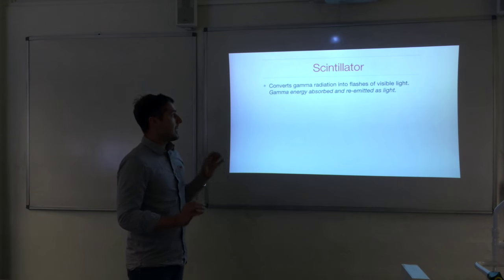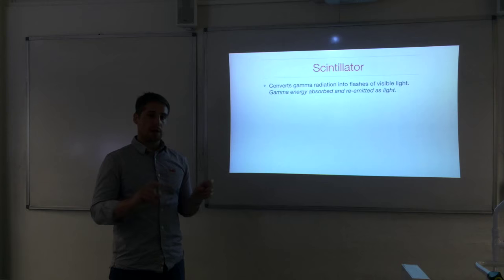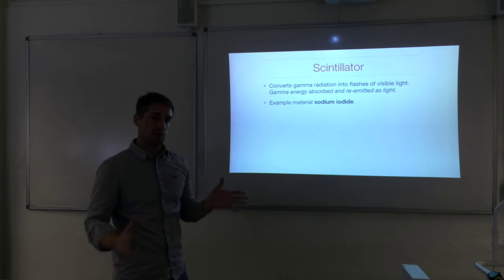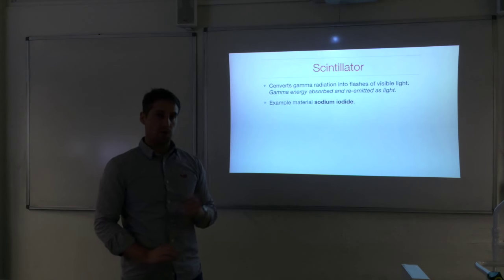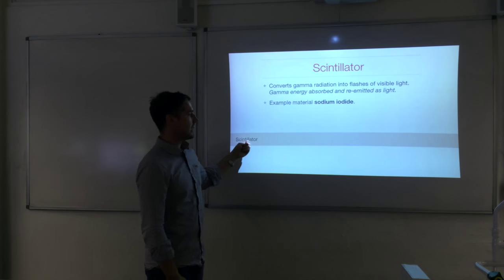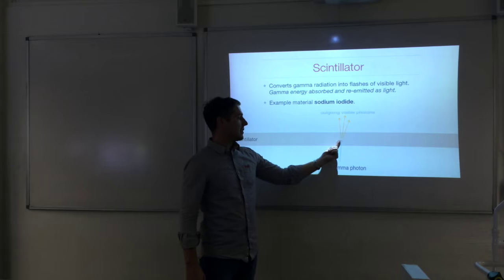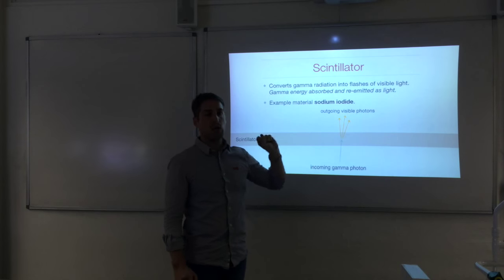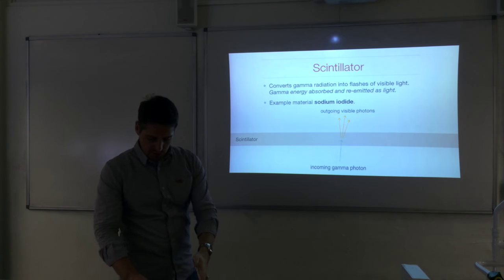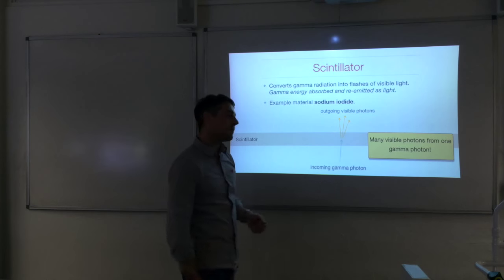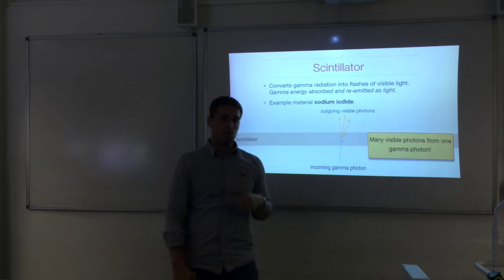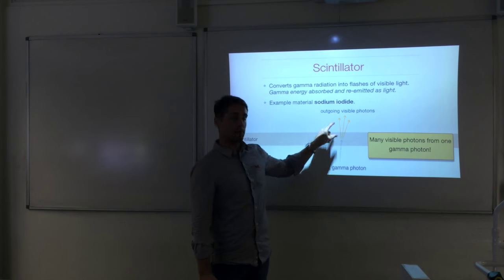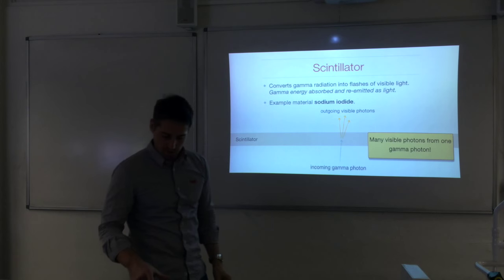The scintillator converts gamma photons into many visible photons. The energy is absorbed in a crystal such as sodium iodide and re-emitted as light. An incoming gamma photon is absorbed and many visible photons are emitted — a flash of light. It is important to appreciate that you get many visible photons from just the one gamma photon because the gamma photon has high energy while visible photons have low energy, so conservation of energy requires more of them.